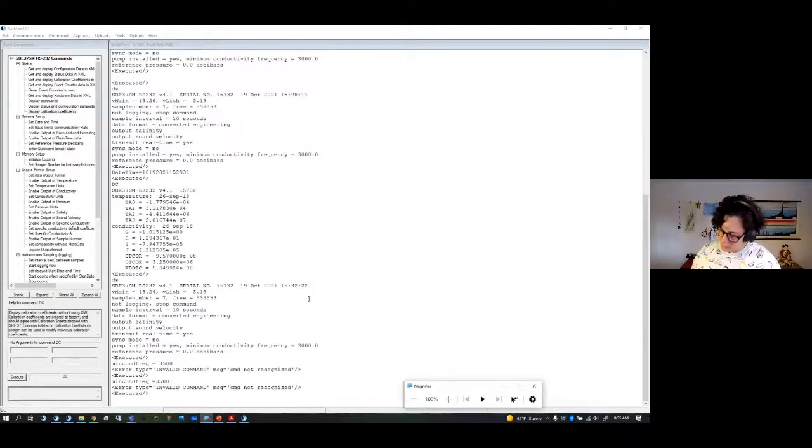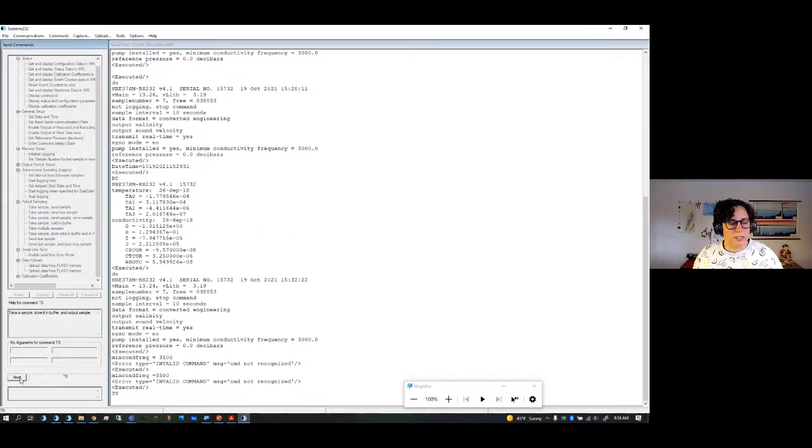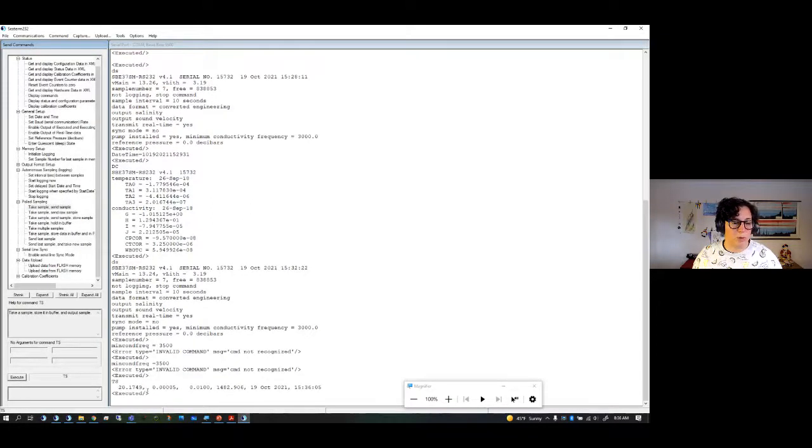Okay. And then the last thing you want to do is actually take some data, so you want to make sure it makes a little bit of sense. You can take a sample here, polled sampling. The TS command is really common. I don't know if you could hear that, but the motor just went on for 1 minute. It tells you some information here. This is your temperature, this is your conductivity, and then here is your conductivity as another variable as well.